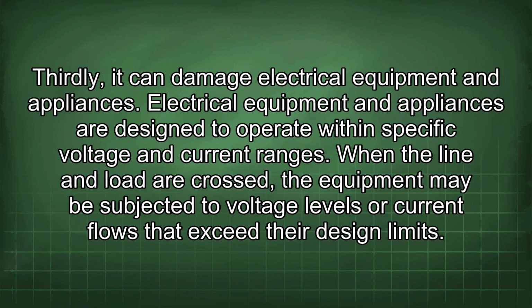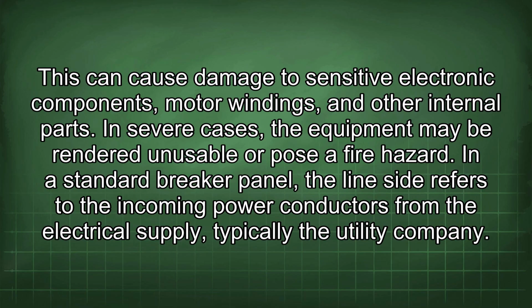Thirdly, it can damage electrical equipment and appliances. Electrical equipment and appliances are designed to operate within specific voltage and current ranges. When the line and load are crossed, the equipment may be subjected to voltage levels or current flows that exceed their design limits. This can cause damage to sensitive electronic components, motor windings, and other internal parts. In severe cases, the equipment may be rendered unusable or pose a fire hazard.